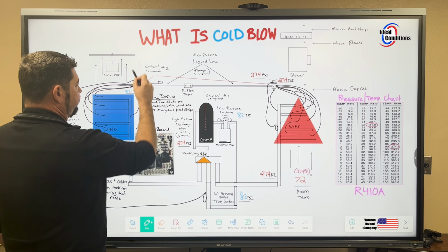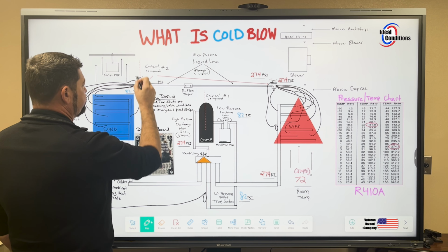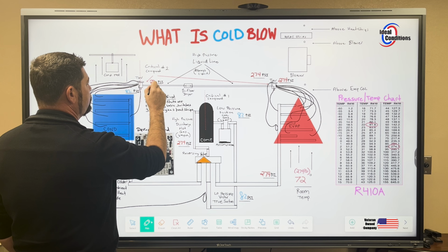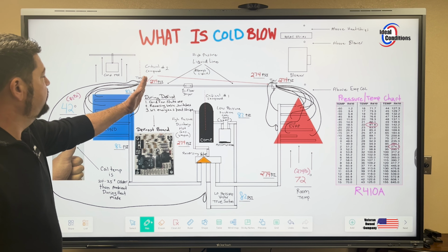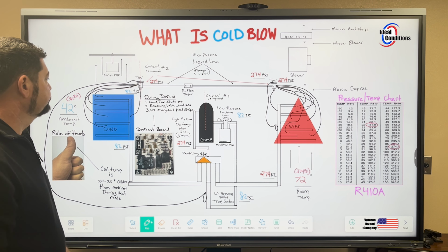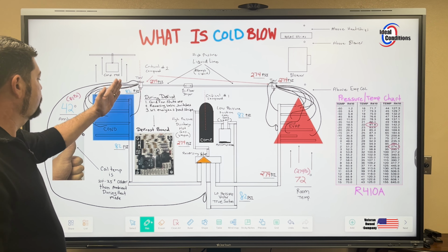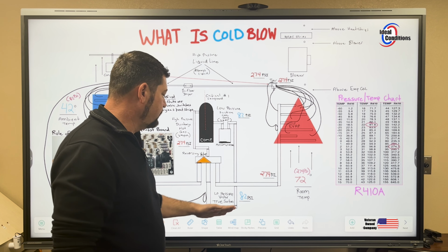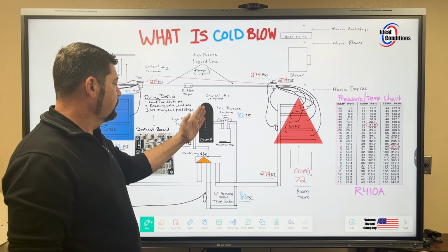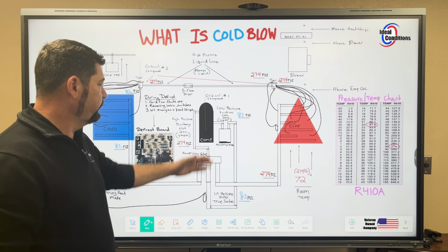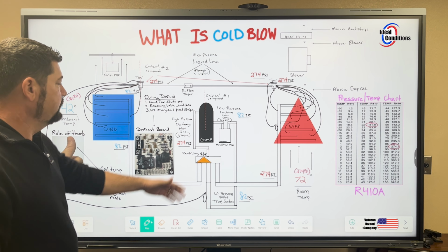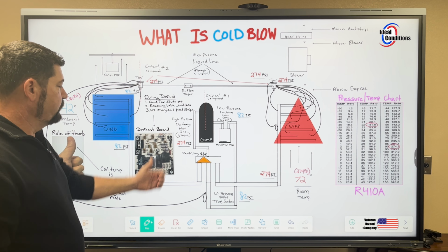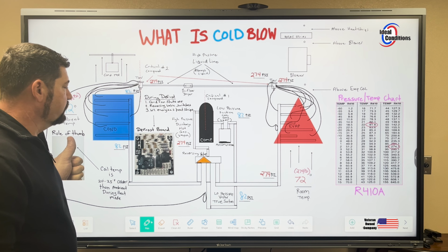Right before we meter, the pressure drop over here at this expansion valve, we are 274, and on the other side of it, immediately we're 82. And so we're 274, 82, 82, all the way through the reversing valve, 82 psi, across the accumulator, into the compressor. We pick up heat of compression. We're still in a vapor state. We have now increased, and we're at 274 psi.